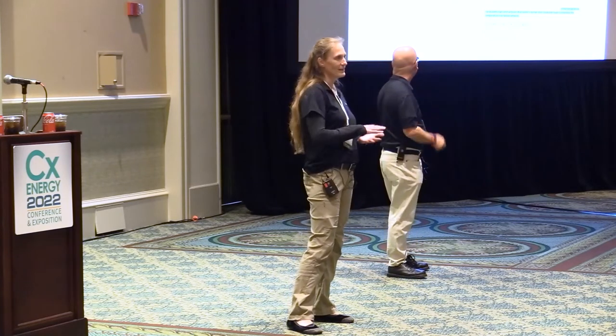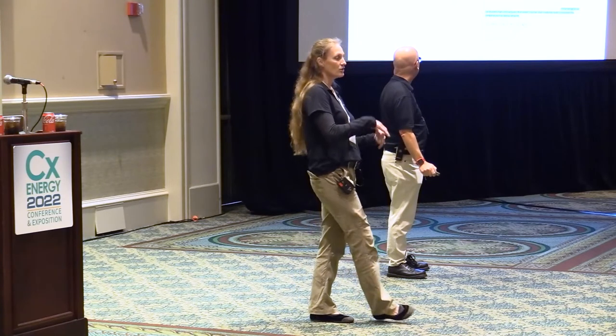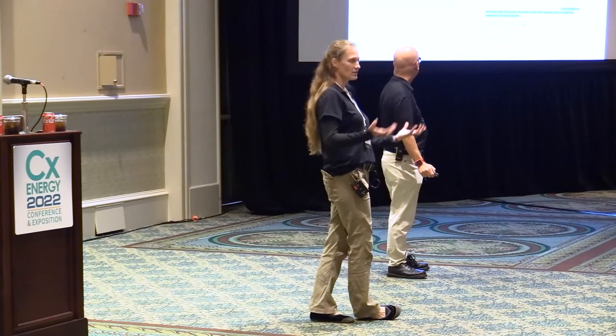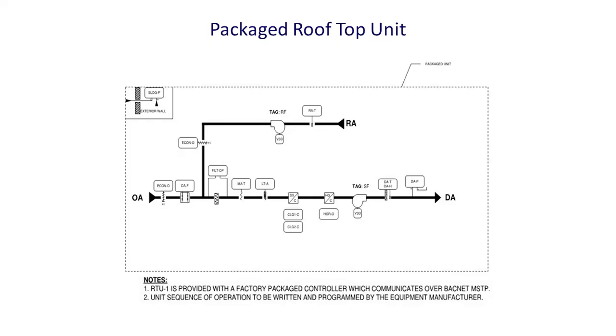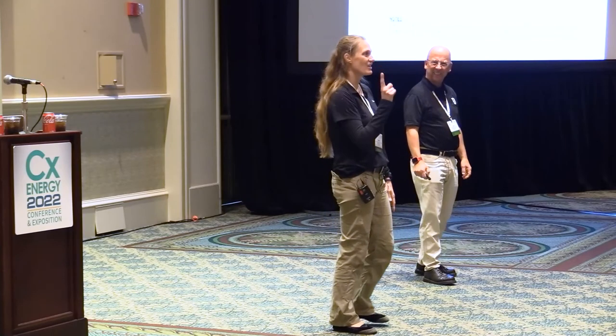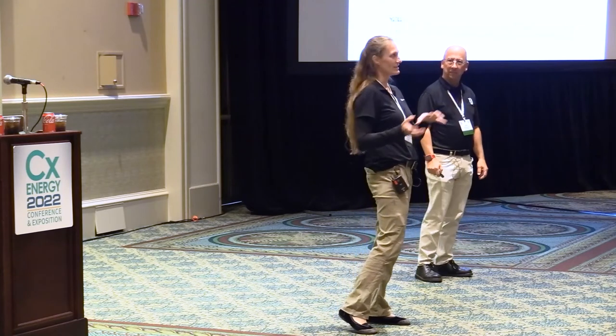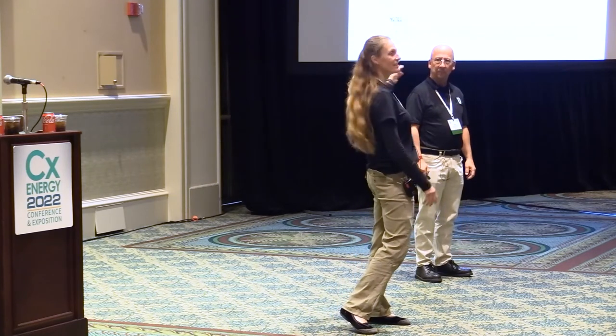Right, and that's kind of a good combined approach: on Tuesdays at 10 o'clock, you can do a runtime equalizer, which just means that the system looks to see which pump has the least runtime and switches that pump to lead at that time, versus it just switching when it is X over the maximum run hours of the other pumps. Here we've got a packaged rooftop unit, and in this case, note number 2, which I'll read to you, says unit sequence of operation to be written and programmed by the equipment manufacturer. Whoa, that's our 1%. Our 1% did not go and copy-paste those control sequences from the designer back into their submittal. So that was really excellent.